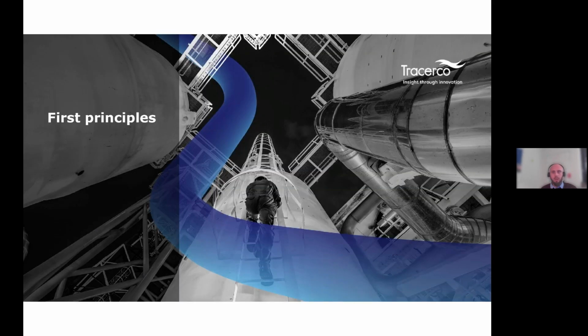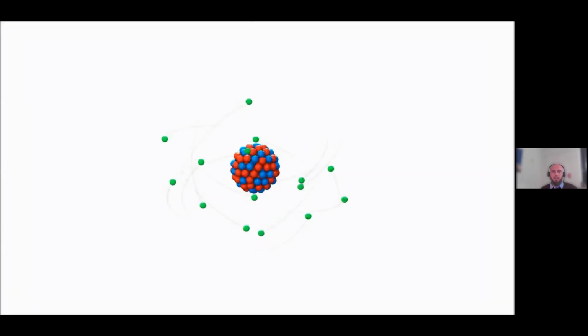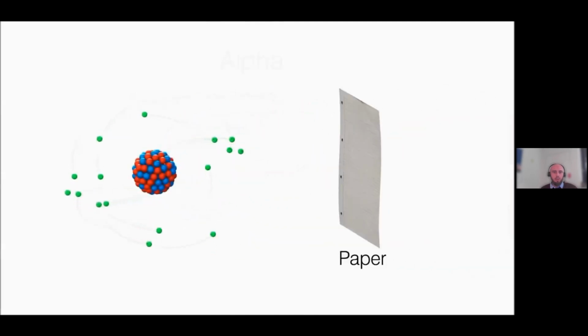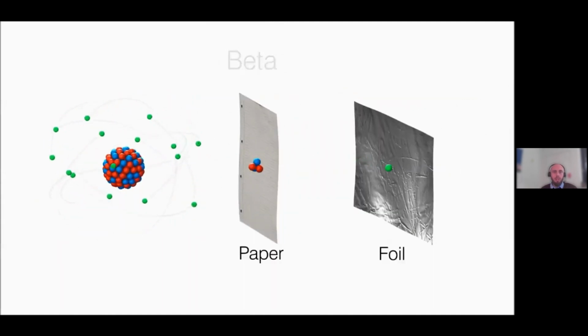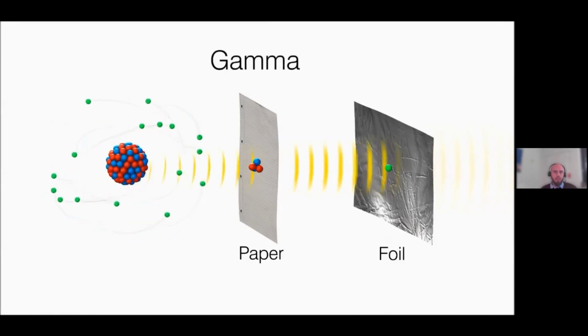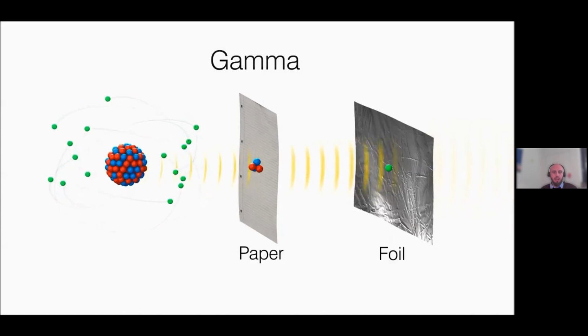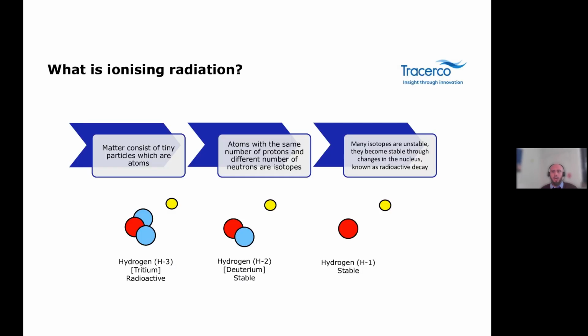So just going to take a quick look at the first principles and a very high-level overview of how our nucleonic technology actually works. The products and services that we supply are mainly radiation-based, and there are different types of ionizing radiation. What's first going to be shown here is an alpha particle, and this will just pass through a little bit of air and be stopped by a piece of paper. The second, the beta, won't be able to go through foil, but is a little bit more penetrating than alpha. And then what we actually use is the gamma ray. This gamma ray is something that is not stopped by anything, it's just attenuated or reduced. This is a very penetrating one, and this is what we use when we measure our instruments. It's this attenuation that we measure when it comes to the products and services that we supply. And by looking at the change in measured dose rate, we can determine many different process variables in the instrumentation systems.